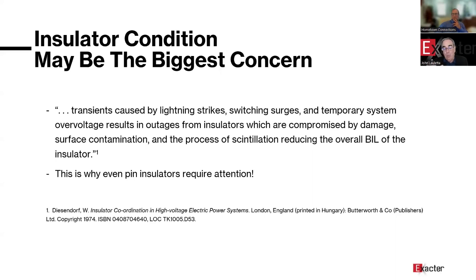And if that one pin insulator is contaminated and is emitting these RF signals and the signature is correct, and you leave it in, that's where you're going to have a flashover. That's where you're going to cause the circuit outage based upon maybe your work, your switching transients on your system. That's why even these $7 pin insulators got to get out of the system if they're contaminated and could be an incipient fault.